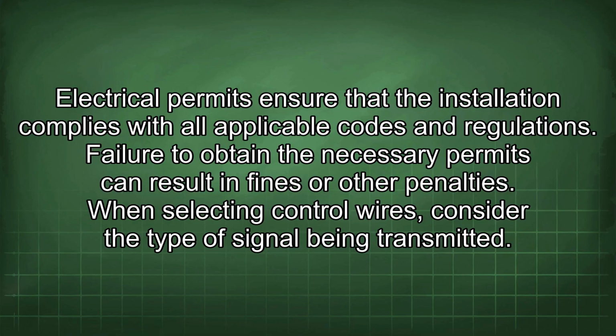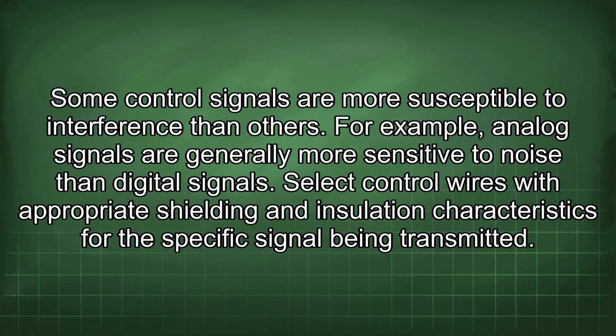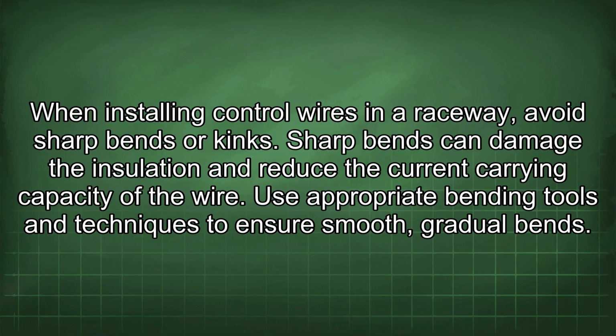When selecting control wires, consider the type of signal being transmitted. Some control signals are more susceptible to interference than others. For example, analog signals are generally more sensitive to noise than digital signals. Select control wires with appropriate shielding and insulation characteristics for the specific signal being transmitted. When installing control wires in a raceway, avoid sharp bends or kinks. Sharp bends can damage the insulation and reduce the current carrying capacity of the wire. Use appropriate bending tools and techniques to ensure smooth, gradual bends.